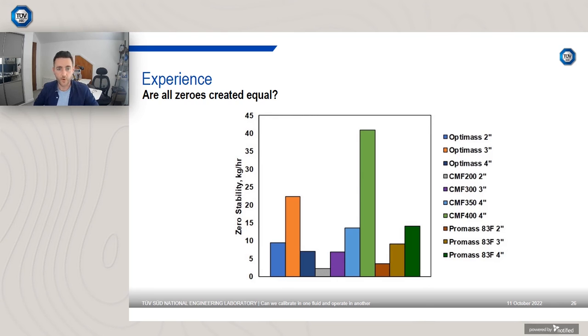So the other question is, are all zeros created equal? I've got 3 different manufacturers here, their specifications for their zero with respect to meter size. I've got 2, 3 and 4 inch for 3 different manufacturers. On the y-axis I've got that zero stability, so that's the maximum permissible zero that you should be looking to achieve for a suitable operation of your device. And you can see that it varies significantly between vendors, but also varies with respect to meter size, partly down to the tube geometry and the specification of the meter ultimately.